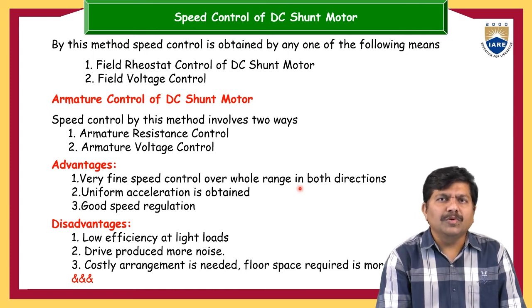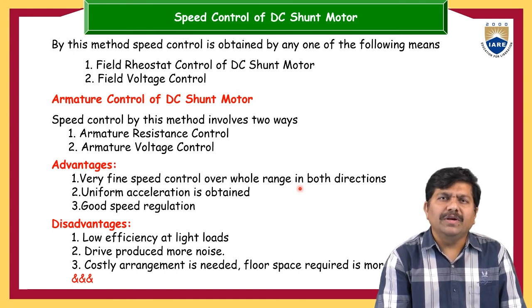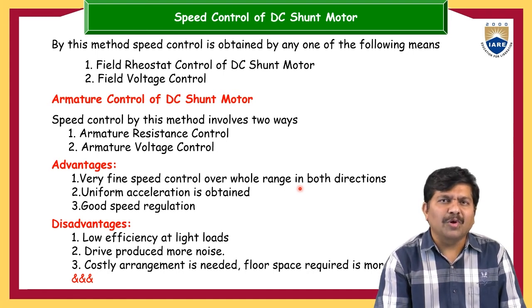So the drive produces more noise. If you control by inserting external resistance in series with the armature, a hissing kind of noise will increase. It is also a costly arrangement, because now we are playing with the armature. If something goes wrong, it is not an advisable control method. That is the reason, because some protection arrangements also have to be taken care of. So a costly arrangement is needed. More floor space is also required. So these are a few disadvantages and advantages.